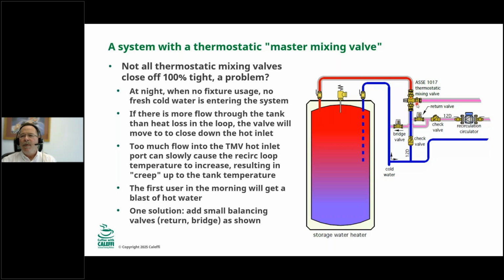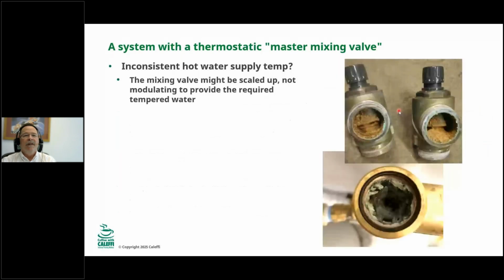A problem we hear about related to master mixing valves in our technical support center here is, the valve used to work great. It was fine for 6 months or a year, and now we have inconsistent hot water supply temperature. Usually, what we find is this: bad water conditions, poor water quality can cause a valve to look like this on the inside when you take it out. It can get scaled up, it'll get stuck, or it'll be choppy. It'll open a little bit or not open a little bit, and basically it's getting locked up.